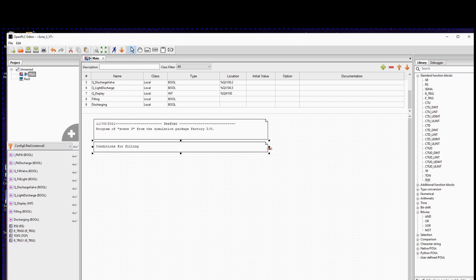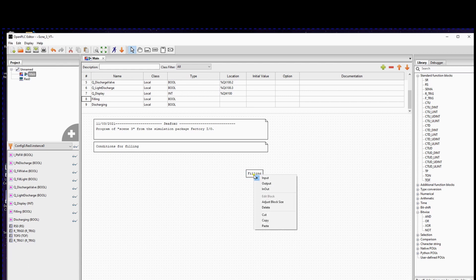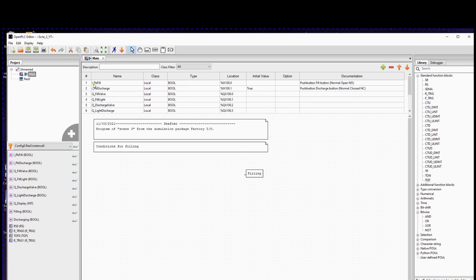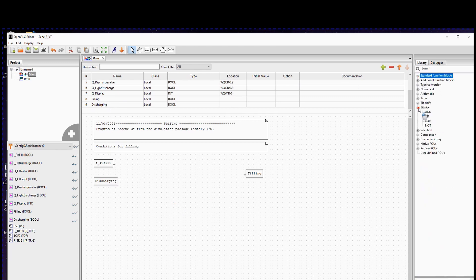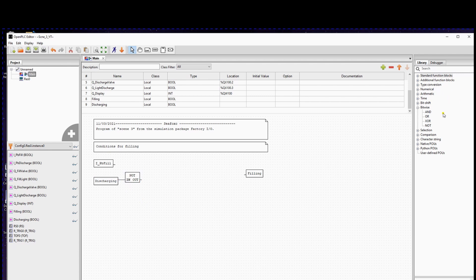One of the conditions is that we press the push button to fill, so we drag it from the variable list to the grid. In this case, the variable filling is an output in the meaning if we want to change the state of the variable. If the connection is not to the left, you right-click on it and set the variable as an output. We also don't want to fill if the installation is already discharging. So if the status is NOT discharging, we can proceed to fill. We go to the library on the right and drag the NOT function block, and connect it to the variable discharge. Now we can use an AND port to connect both signals. Only if both signals on the AND port are true, the output of the block will be true.